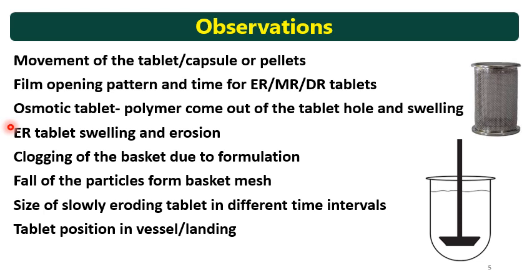These observations are important for formulation optimization and selection of dissolution parameters. Observe extended release tablet swelling and erosion. Check whether there is choking or clogging of the basket due to the formulation, and whether particles coming out of the formulation are falling from the basket mesh inside the dissolution bowl. Check the size of the slowly eroding tablet at different time intervals. Observe the position of the tablet in the vessel — if the tablet lands at the side rather than the center, it will experience different hydrodynamics and give faster dissolution results.